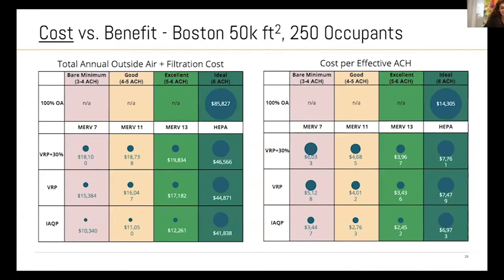More than this, there's an ability to display the data nicely for your clients. And this is something I always get: how can we show our client, or the parents, that we did enough? So here is basically the annual outside air plus filtration cost, including the maintenance. And the bubble size, I apologize if there is a problem with the formatting, but the bubble size is the cost. The way you read this is: 100% outside air, you can achieve 6 air exchange rate, you pay this much, and specifically in Boston.